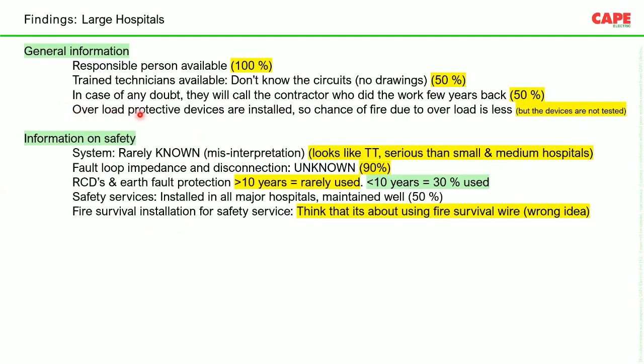In these cases, overload protective devices are installed. Protective devices such as, from the starting, air circuit breaker, molded case MCCB, MCB, fuses, all those things are installed. So the chance of fire due to overload is mostly less in this particular case because proper devices are there. Unfortunately, the devices are not tested. So we really don't know whether these devices will trip or not.